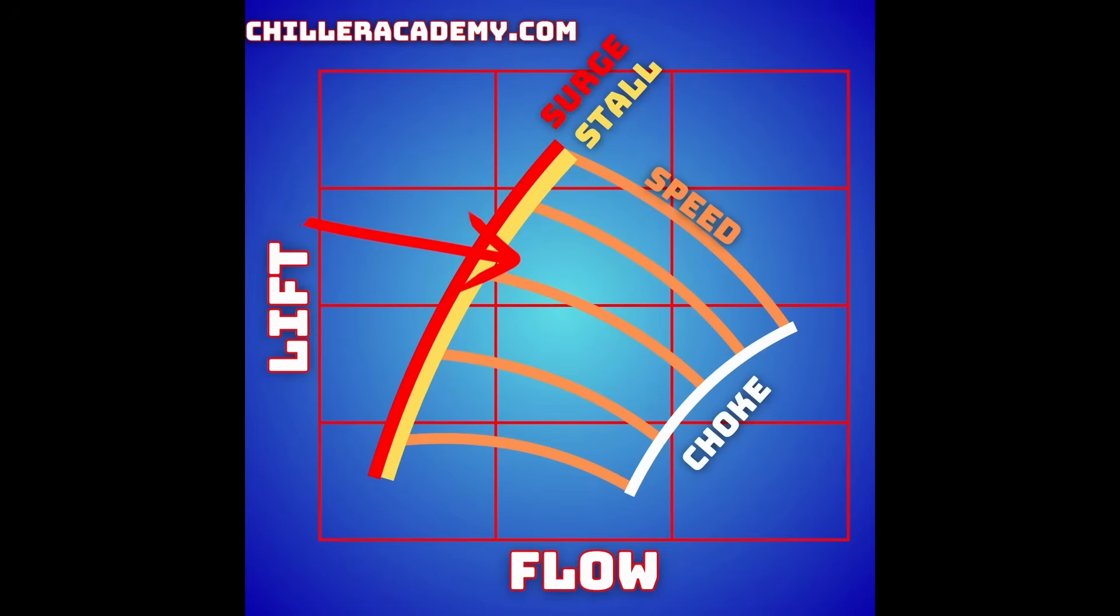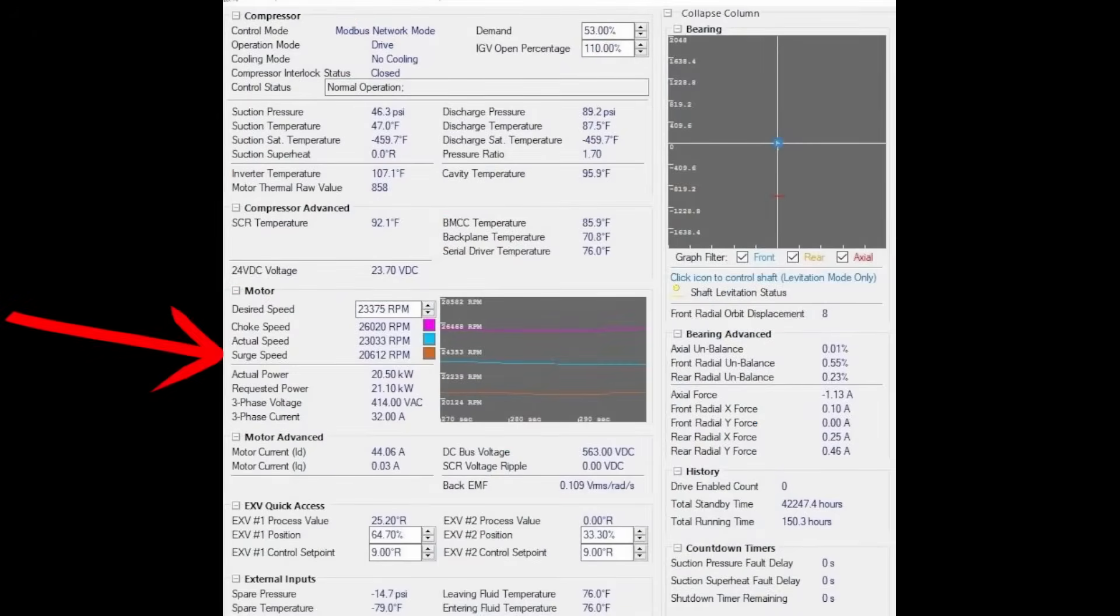I'm trying to articulate it better. I'm not as proficient at articulating choke as I am some of these others. With choke, essentially, I think of it as the compressor or the impeller is getting starved. It's trying to flow more than it can based off of the lift conditions, which creates its own type of stability issue.